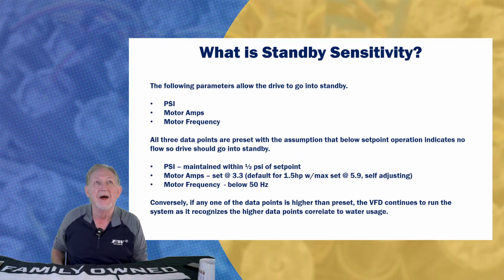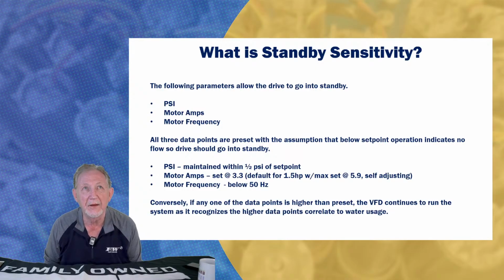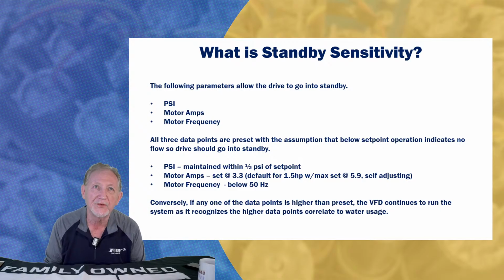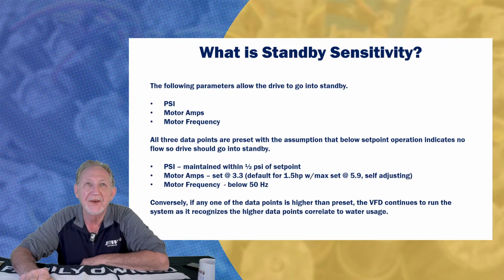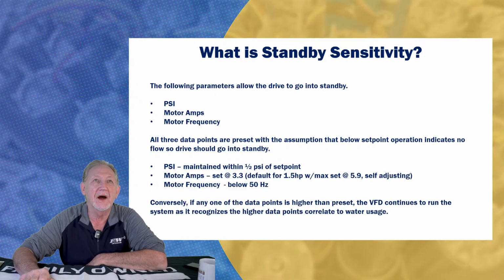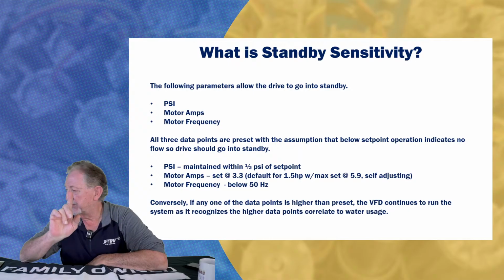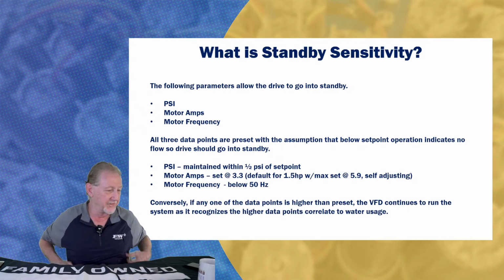So in other words, those three thresholds, right? PSI, motor amps, and motor frequency. When we end up operating below those three thresholds, that drive's going to go into standby, all right? Go into standby. Conversely, oh, there's your code word for the day, folks.